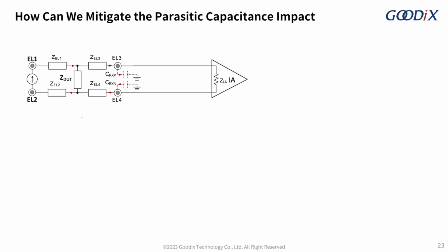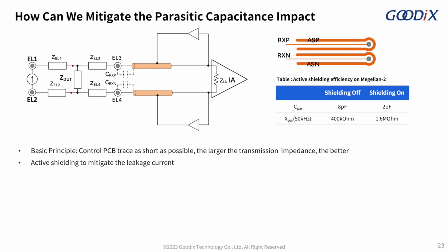There are two ways to reduce the impact of parasitic capacitance. First, reduce the parasitic capacitance as much as possible by using short, high-impedance PCB traces. The second way is to reduce the charge through the capacitor. This can be achieved by active shielding. Change the reference to the active shield instead of the system ground.